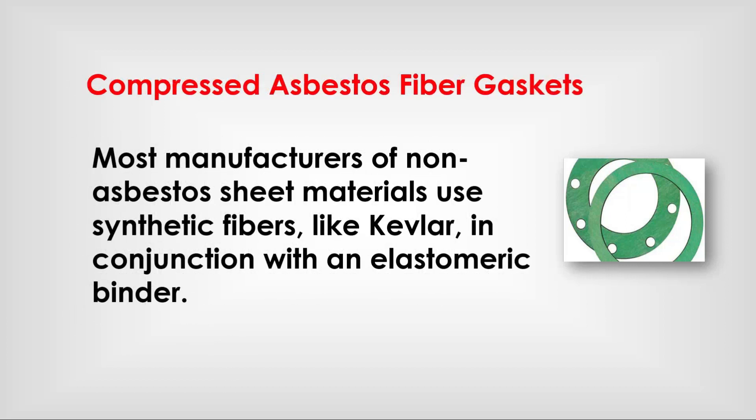Most manufacturers of non-asbestos sheet material use synthetic fiber like Kevlar in conjunction with an elastomeric binder. The elastomeric binder makes up a large percentage of this sheet and thereby becomes a more important consideration when determining applications.